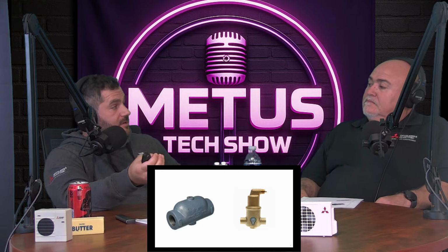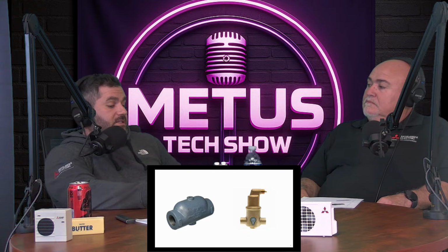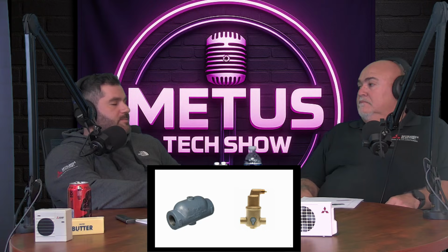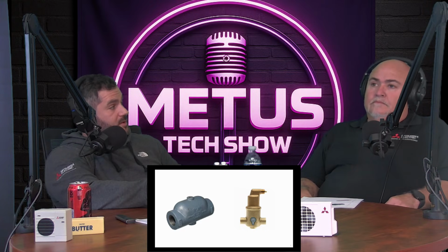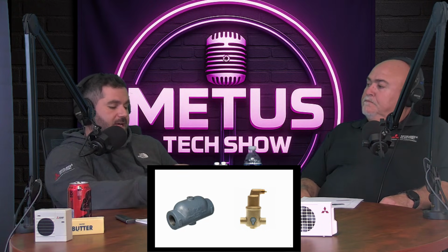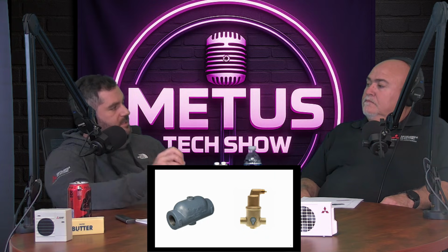And if there's nowhere for it to go, it will cavitate your pump, and then you won't have any flow of water through your system. And so these are specifically designed to catch those microbubbles. They're not going to purge a whole system for you. They're specifically designed to catch those system microbubbles that occur during operation.